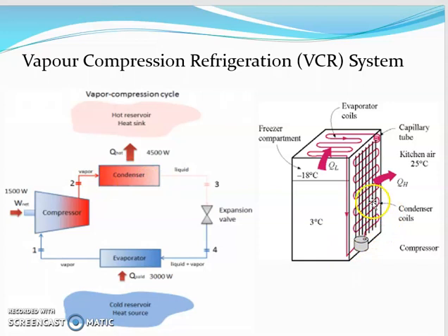So the condenser coil is over here. So within the condenser what will happen? The refrigerant rejects the heat to the normal atmospheric air through this air to this air, and so over here it gets converted into liquid state at high pressure and high temperature itself, and then that passes to the expansion device or capillary tube. So within the capillary tube or expansion device what will happen? It reduces the pressure and temperature of the refrigerant, and then the refrigerant again passes to the evaporator, and the cycle repeats. So this is the working of VCR system.